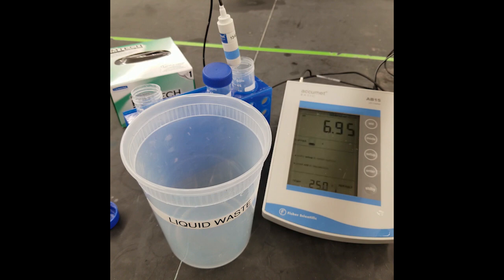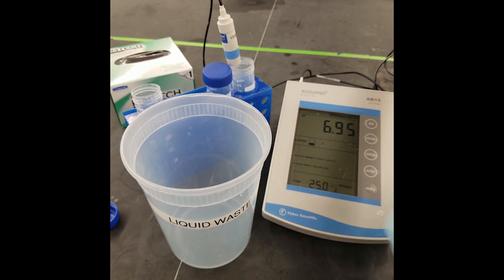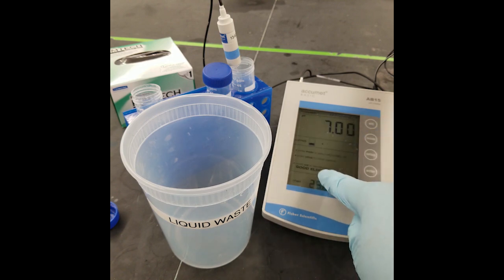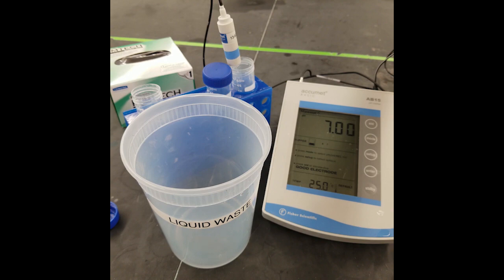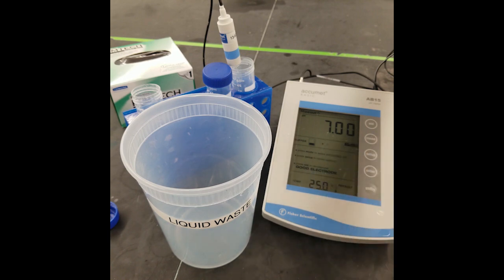We're going to hit standard once to enter into standardization mode. And then again, once we verify that the pH is stabilized, we'll hit standard again, and we're just going to get this quality check reading saying that we have a good electrode and it's standardized well. And then we can also see on the display the numbers 4 and 7, which correspond to the standards in which the pH meter has been calibrated against.